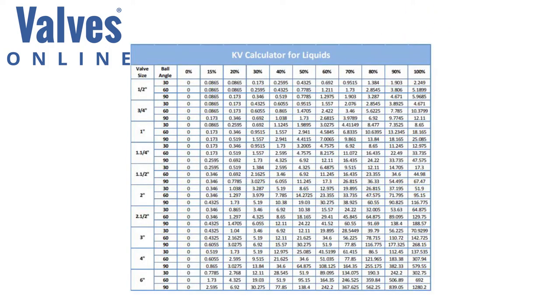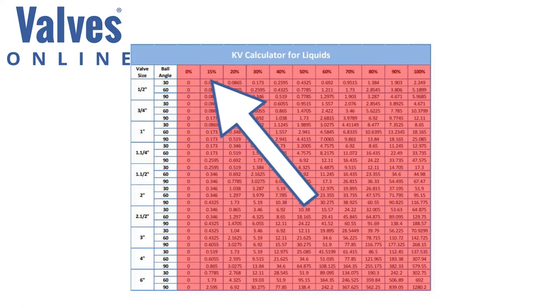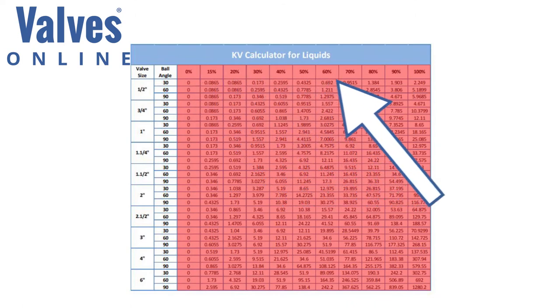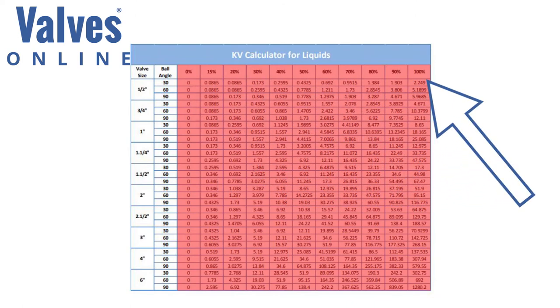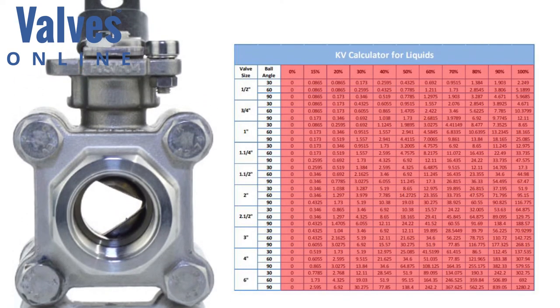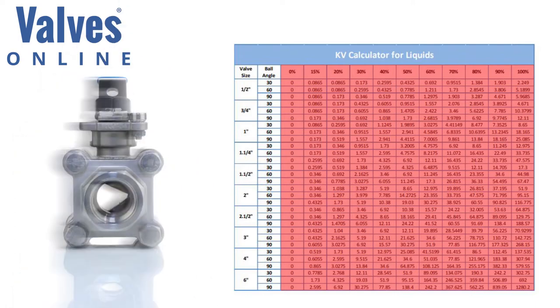The figures displayed under the percentage opening columns are calculated coefficients of flow kV, measured in cubic meters per hour of water, based on a temperature of 20 degrees Celsius with a pressure drop of 1 bar.